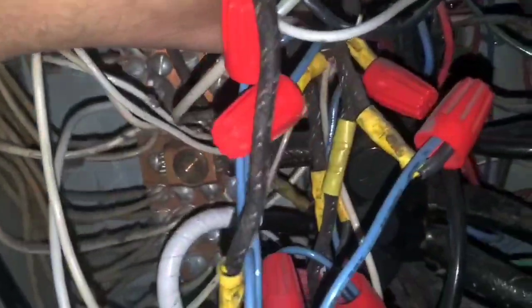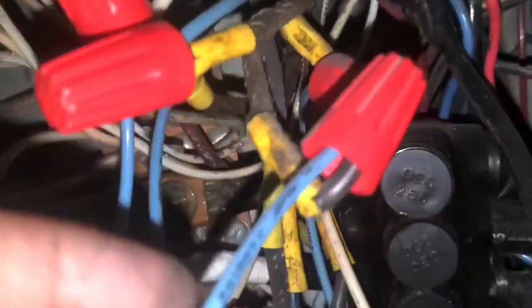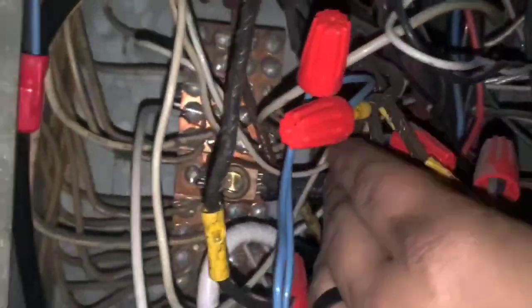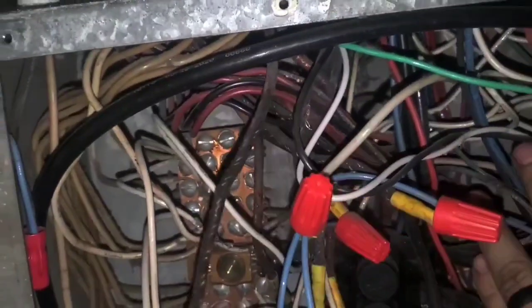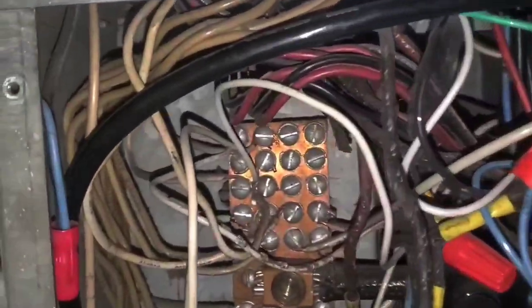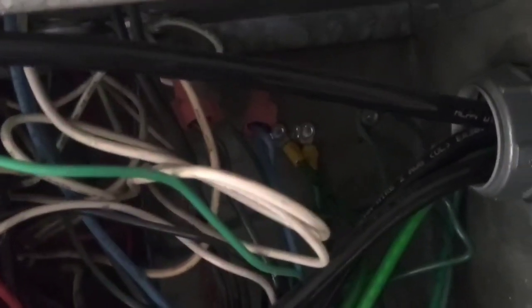Now I can hook up a little coiled up MC cable right there. I gotta move all this stuff out of my way so I can get to that neutral bar right there. These are all a bunch of old cloth wires, and you see some of them have little naked spots. So I can get to the neutrals now. Going in through that punch out with that wire. There's our hots. There's a neutral and the ground just ties up over here. You see it?